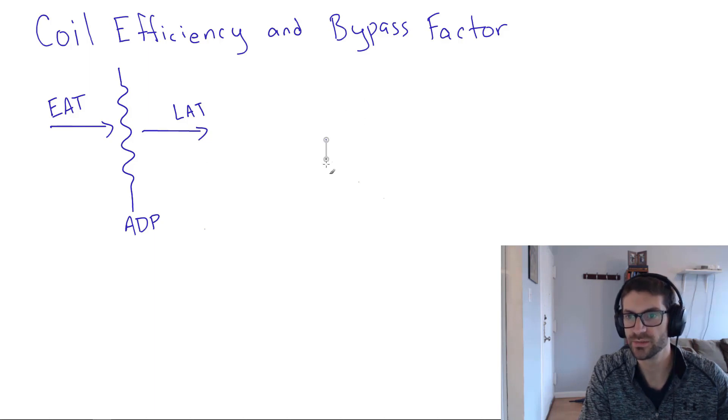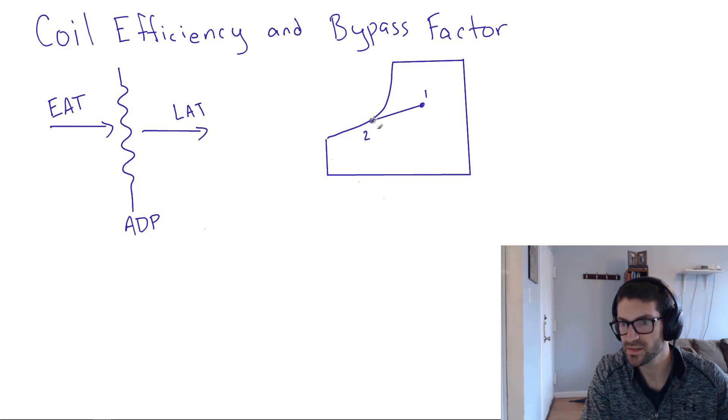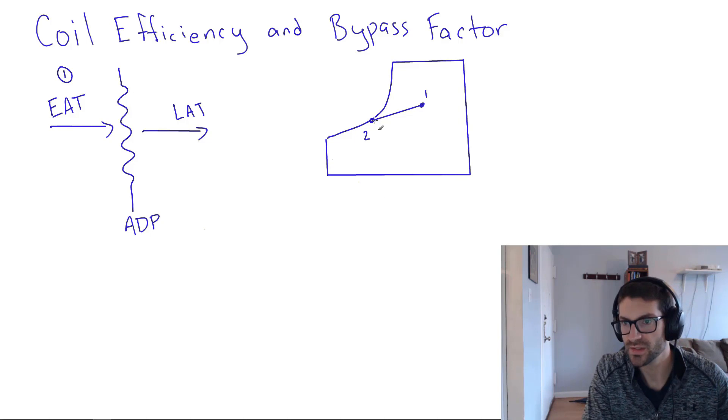And to illustrate that, we can use psychrometric chart. So let's imagine we're starting at some state one and our goal is to cool down to some state two. Well, that's pretty idealistic. That supposes that we're going to be able to cool all the way from that entering air temperature, that's our state one, down to state two, where state two is on the saturation curve. So that would be the apparatus dew point.